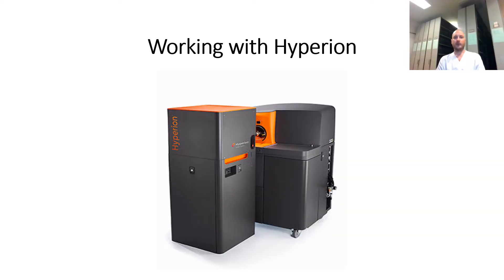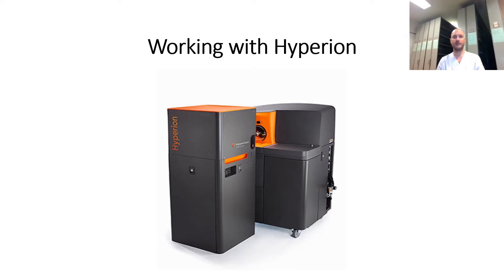Working with Hyperion involves several different steps, starting with selection of antibodies that you want to use, followed by applying a master mix with all the antibodies to tissue samples. Then the tissue slides are put into the Hyperion machine itself. For this first part I want to explain a little bit about the machine itself and how it works. For the next part I'll go through in more detail the different steps before samples are put into the machine and what happens after.